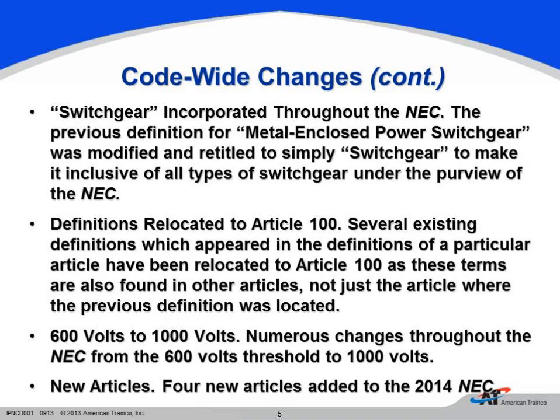Before we do leave this slide and get to the new articles, I would like to mention one more definition, readily accessible. They have changed that up. So historically, readily accessible has been we can walk right up to it, put our hand on it. We don't need any ladders. We don't have to move any ceiling tiles. And so what they have added here is that we also don't have to use any tools. So if we need to use a tool to access something, it is not going to be readily accessible. It would still be accessible. We could still get to it, but it would not be readily accessible.